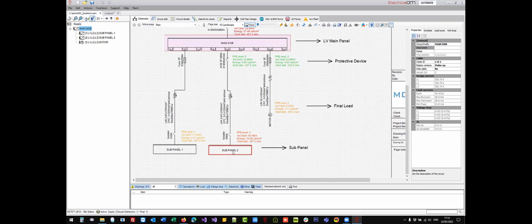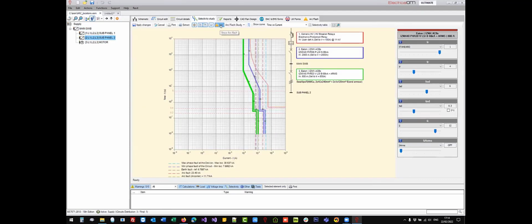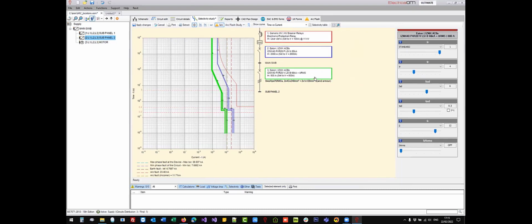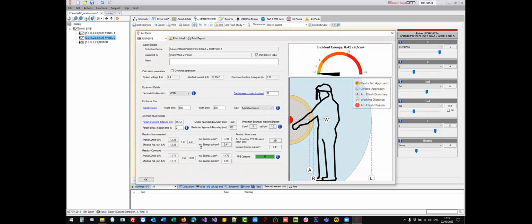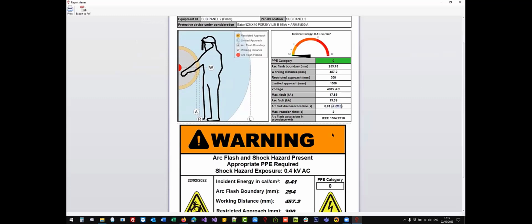hazard during the maintenance. So if I access this panel and then go to the selectivity study and enable the arc fault here, let me remove the other faults. So it's clear that we're dealing with the arc fault. Okay. If I select this Eaton device, you'll see that there is an ARMS option here. So we can enable this ARMS from here, and this will not override any selectivity checks done, but it will be only considered for the arc flash assessment. So now if I access my arc flash, I see that this is disconnected instantaneously. And if I go to my reports, I will see that the ARMS option has been used.